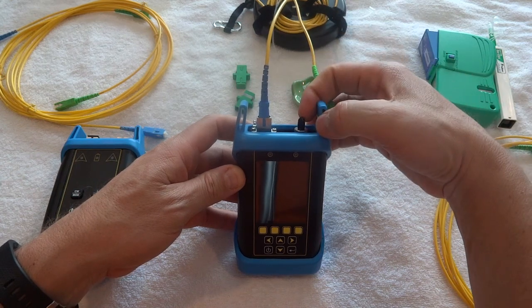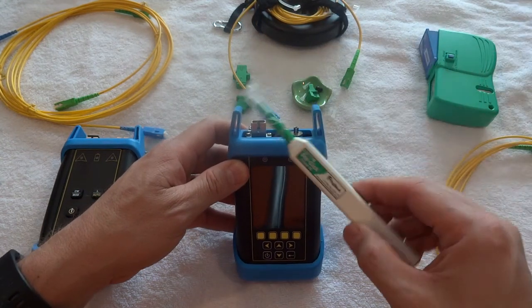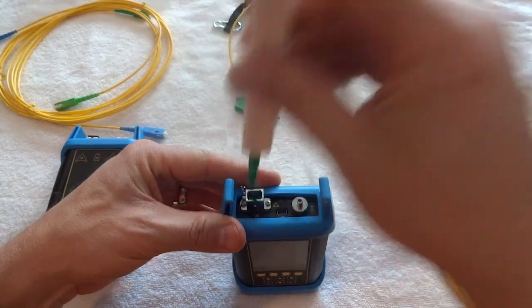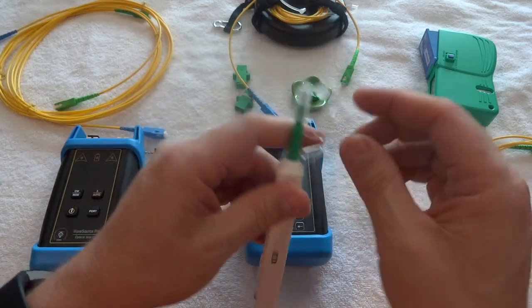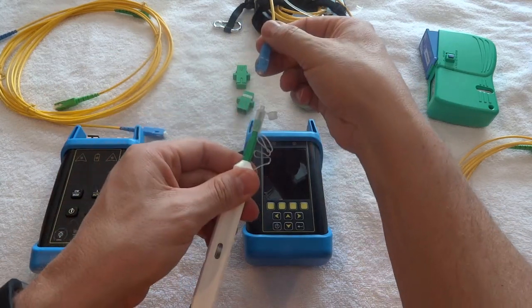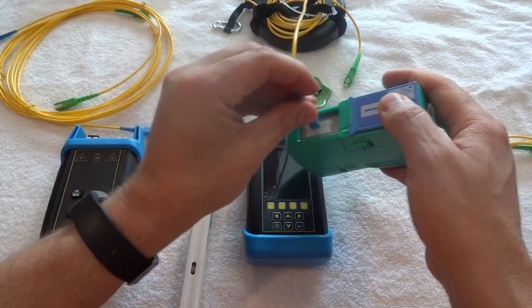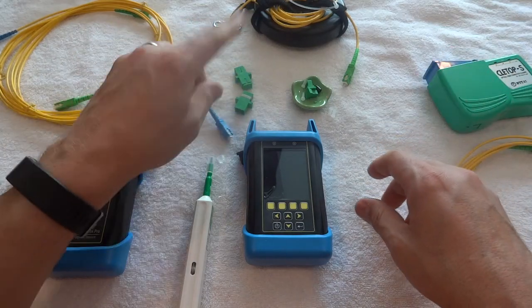Before plugging everything in, I'm going to use my cleaners. We have the Fujikura one-click cleaner — you just pull the cap off, go straight down into it, and give it a couple of clicks and that'll clean it. It can also flip up to clean the cables themselves. If you've got a lot of cables to clean, we also have these Cletop units — you open them up and just scrub and clean. Every time you pull one of these out you should be cleaning it.